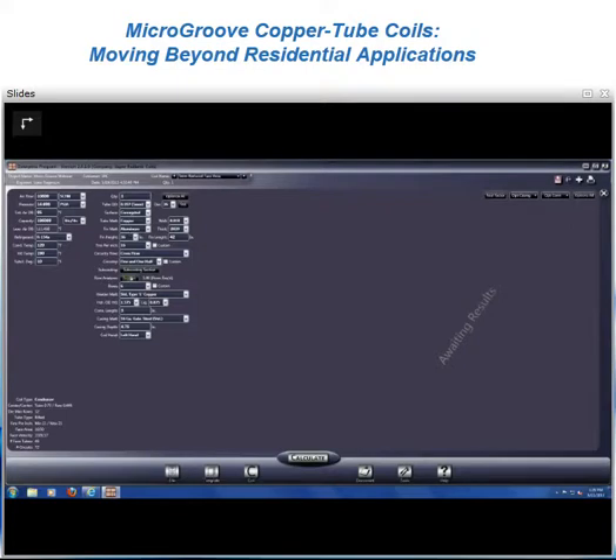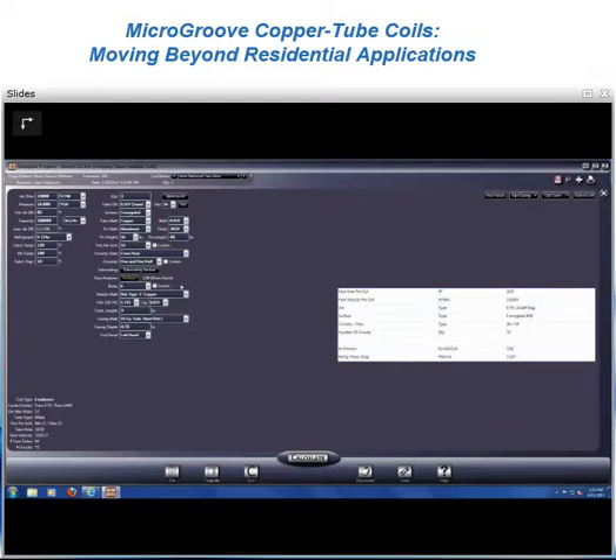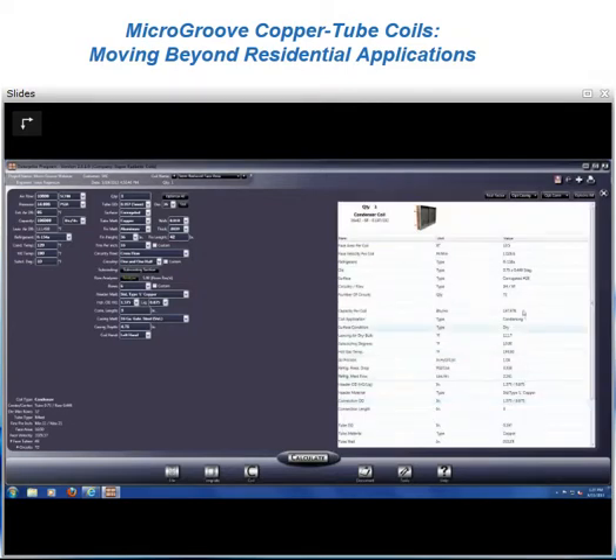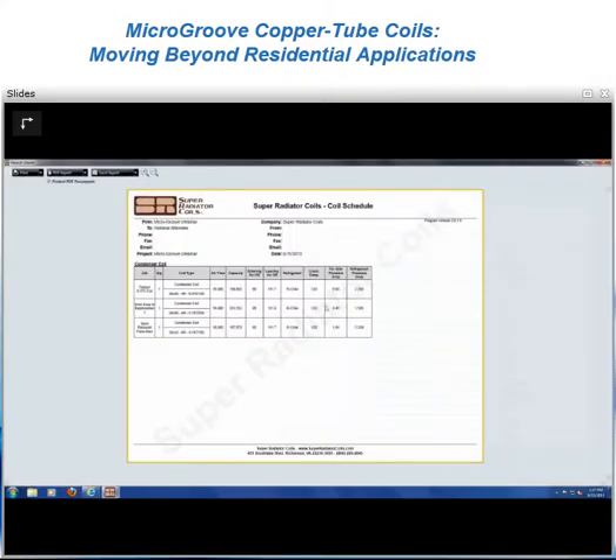And as before, we've put in the information on the materials of the coil. We'll analyze this, and because our face velocity is higher, we would expect that it's more rows. So it's 5.9 rows. So we'll analyze and calculate that as a 6-row coil. Just a quick couple of highlights here. There's the 197,000 BTUs per hour that we were looking for. Because we do have a higher face velocity, the air friction is increased. It's up to 1.4 inches. So that's something we need to consider in our design. So let's take a look at that compared to the drop-in replacement, the current 3/8. And you see a quick side-by-side comparison here.